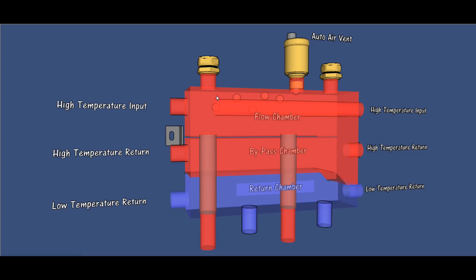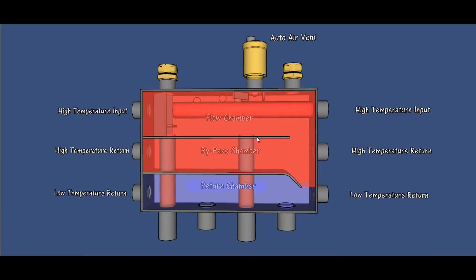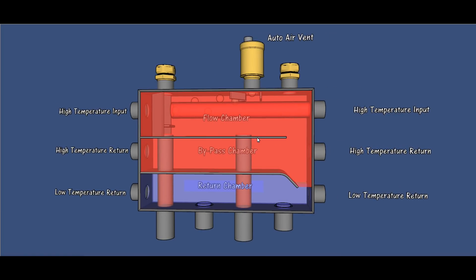What you have is two distinctly different temperatures of water. You have a constant de-aeration unit because this is a bigger area compared to the pipe feeding it. The water velocity slows down, the air travels to the top, and every time the water passes through the manifold it's a de-aeration unit.